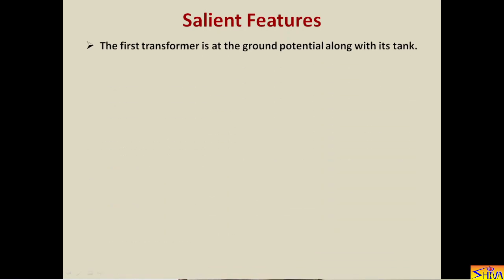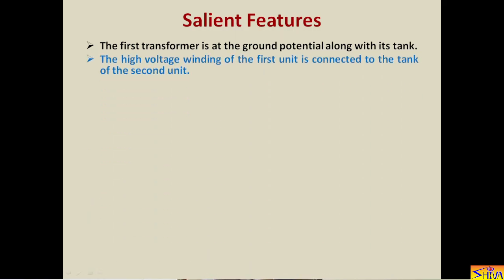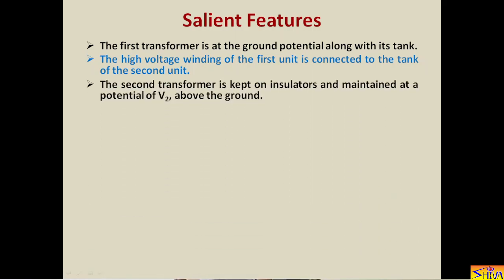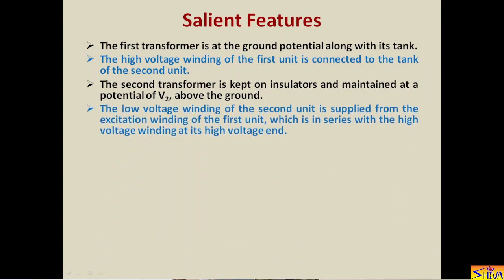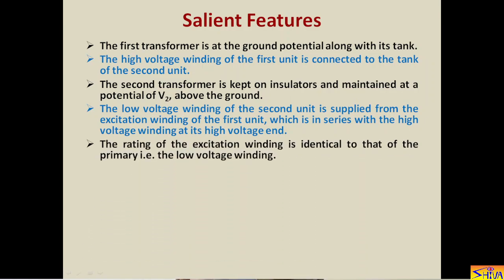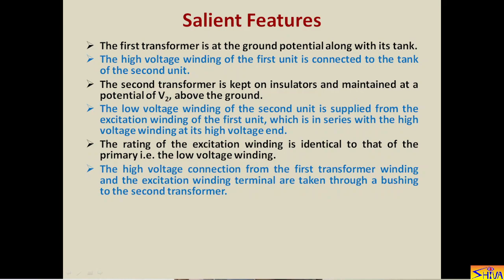The first transformer is at ground potential along with its tank (body). The high voltage winding of the first unit is connected to the tank of the second unit. The second transformer is kept on insulators and maintained at a potential of V2 above ground. The low voltage winding of the second unit is supplied from the excitation winding of the first unit, which is in series with the high voltage winding at its high voltage end. The rating of the excitation winding is identical to that of the primary low voltage winding. The high voltage connection and the excitation winding terminal are taken through a bushing to the second transformer.